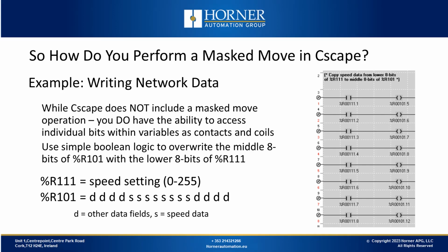By employing Boolean logic, we can selectively copy bits from one variable to another, specifying the source and destination bit numbers. In Cscape, to achieve this, especially in the traditional register-based approach without utilizing user-defined function blocks, we create a separate rung of logic with a coil and a contact for each bit we intend to write from a source to a destination.